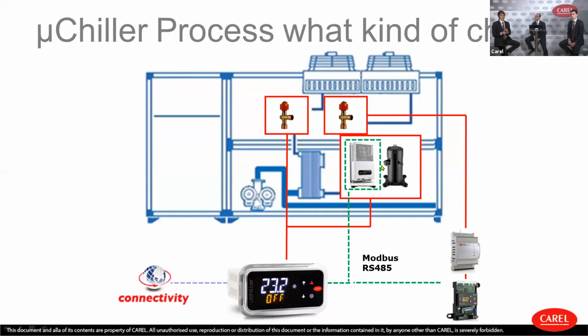So it's your choice. We give you the handles to decide if there's a process priority in the management of your chiller, rather than other thresholds, for example waiting time on restart of the compressor, which in comfort applications tend to preserve the unit and save the compressor. You want to save the process instead. You can select that, it's up to you, it's important, you can pick.